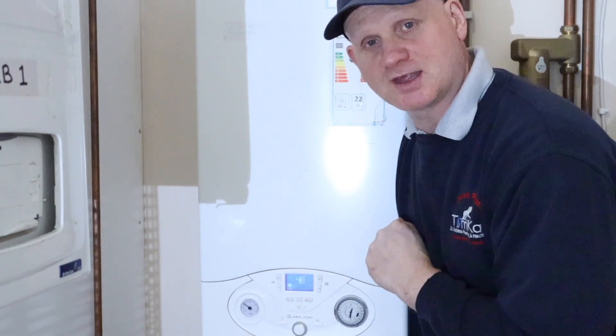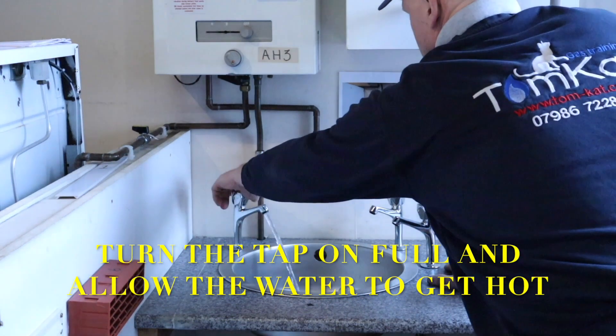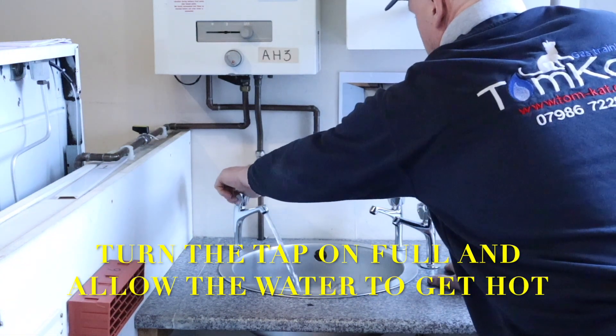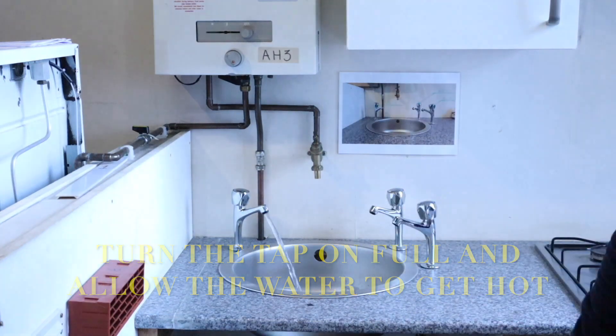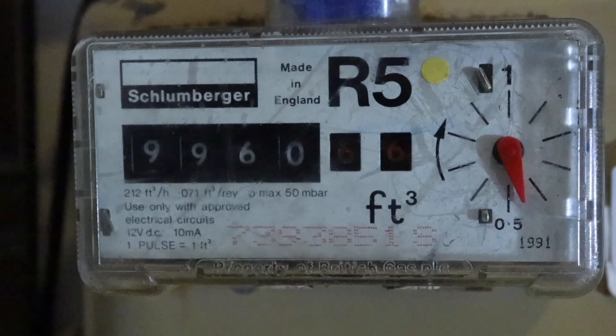Using this R5 gas meter. Now I've got the tap running, I'm just going to wait till the finger goes all the way down to the bottom, and then I'm going to start my stopwatch and time how long it takes to do one full revolution — and we're off.